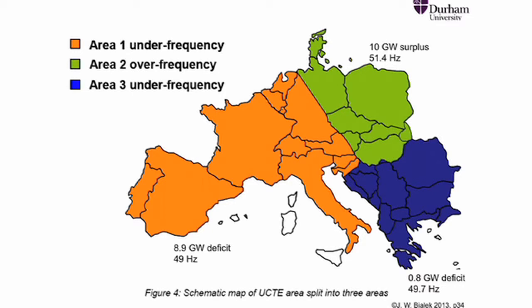What was the result of that? Europe separated into 3 different areas, with 3 different frequencies. Power was exported from the east to the west, so that means there was a surplus of power in the east, and the frequency went up. In the west there was a deficit of power, so the frequency went down to 49 Hz. And in Southeast Europe, it was just a slight deficit.